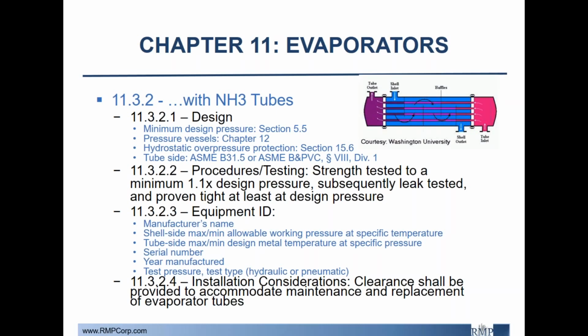The procedures and testing, again, going back to the 1.1 times the design pressure, the leak testing, and the proven tight at design pressure. So there's no reference to the ASME code here. The equipment ID should again be provided by the manufacturers.